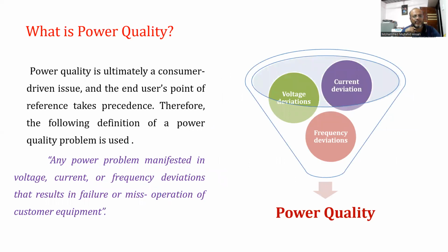But in a very simple way, in our perspective, the power quality definition is this: any power problem manifested in the voltage, current, and or frequency deviation that results in failure or misoperation of consumer equipment. This is our simple definition, and it makes an umbrella for the utility, the consumer, as well as the manufacturer. So any deviation in the voltage, current, and frequency from the standard value that results in failure or misoperation of the consumer equipment counts.